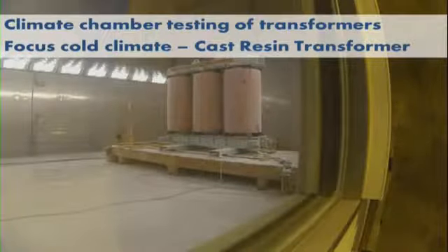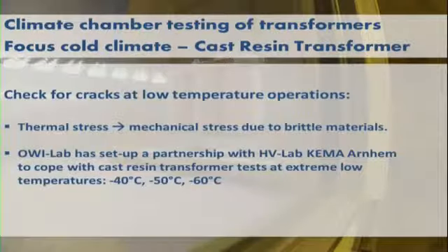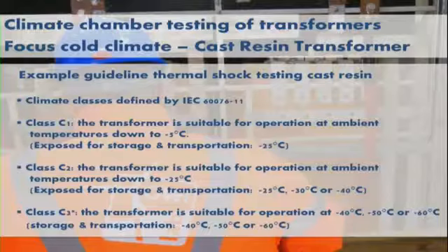Finishing with the cast resin transformer: again, this is one of the cases we did at very low temperatures. We have a partnership there with HV-Lab KEMA Arnhem in order to cope with very extreme temperature testing of these cast resin transformers. The main thing we check is whether there are any cracks because of the brittle materials and the thermal shock. As I explained, there are some certification classes. C1 is not that tough: -5 operational, -25 storage. You have C2, which is -25 operational testing, and class 3 is not really an official class, I think, but some manufacturers, for example for the Russian market, want to test at -40, -50, or -60 degrees, and again you also do the storage test at these temperatures.